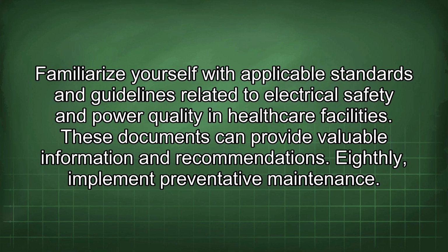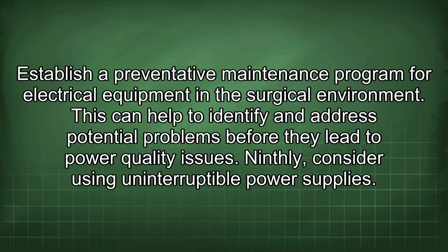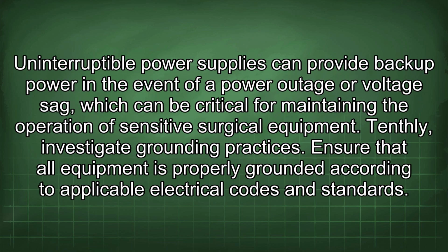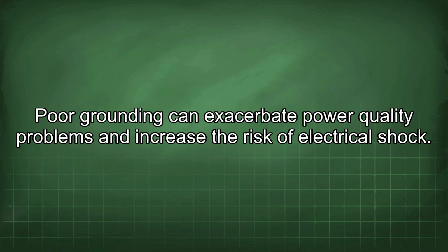Eighthly, implement preventative maintenance. Establish a preventative maintenance program for electrical equipment in the surgical environment. This can help to identify and address potential problems before they lead to power quality issues. Ninthly, consider using uninterruptible power supplies. Uninterruptible power supplies can provide backup power in the event of a power outage or voltage sag, which can be critical for maintaining the operation of sensitive surgical equipment. Tenthly, investigate grounding practices. Ensure that all equipment is properly grounded according to applicable electrical codes and standards. Poor grounding can exacerbate power quality problems and increase the risk of electrical shock.